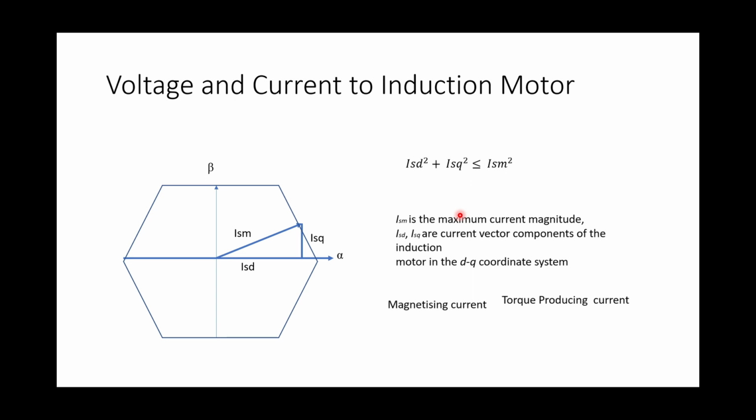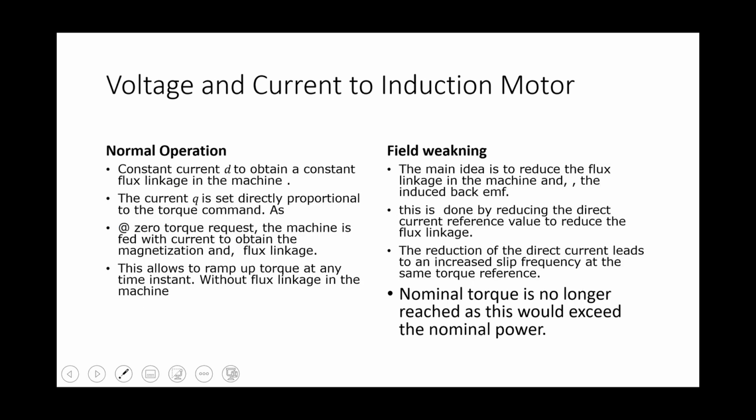Based on the reference values of torque and flux linkage, which depend on the actual machine parameters as well as the operating point, reference values of D and Q currents are calculated, and we compare them in the controller. Finally, we transform back to the instantaneous 3-phase coordinates and calculate the duty cycle of the inverter, and finally you get the output of the drive to reach a certain level of torque or frequency, whichever was required. Hope it is clear to you.